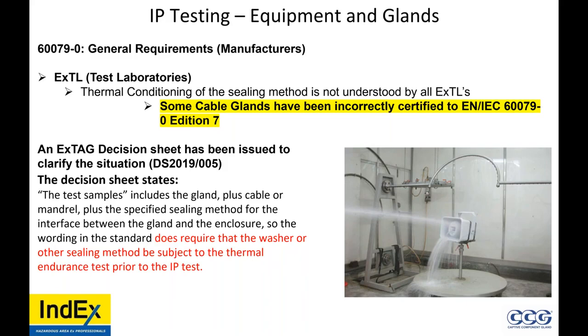Now, there was a decision sheet, an engineering assessment done by the IECEx. Basically, it does require that the washer or sealing method be subjected to a thermal endurance test prior to the IP test. You have to stress it. But I still call into question, when you're doing IP testing, you're doing it on a new device. What about that device in 5 years, 10 years, 20 years? When Samsung tests their phones, let's say the Galaxy Fold, they do testing to see how many years it will last. You don't seem to do that for IP testing. What about the device in so many odd years?